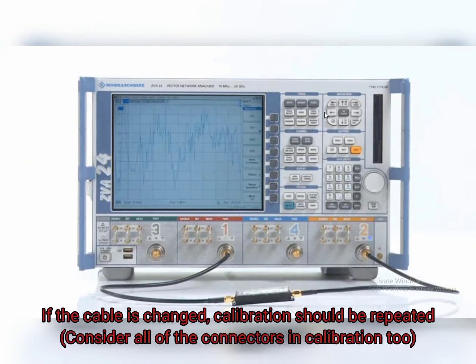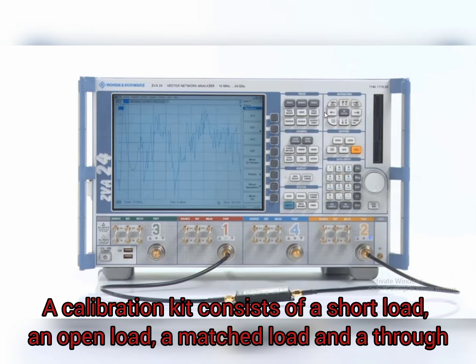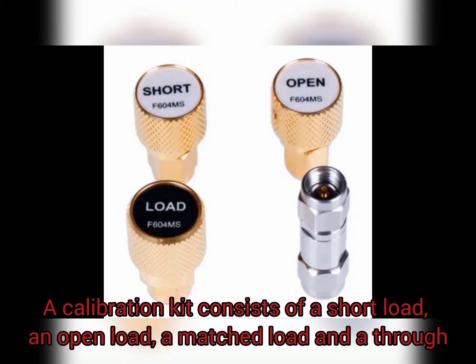If the cable is changed, calibration should be repeated. A calibration kit consists of a short load, an open load, a match load, and a through.